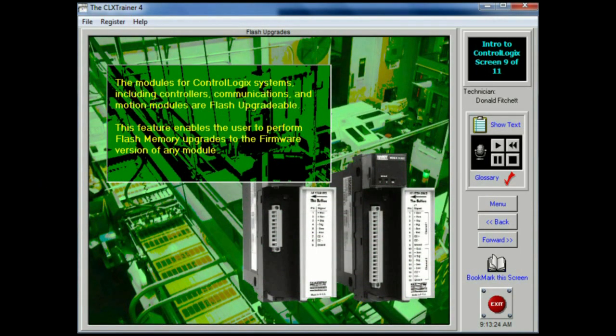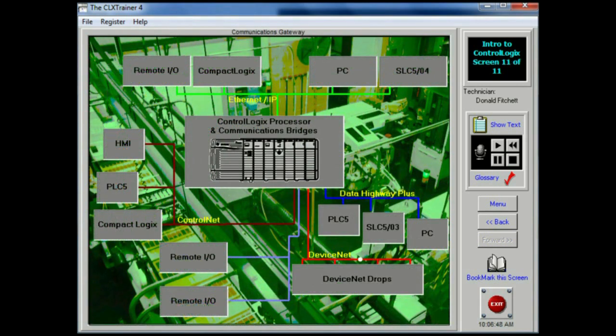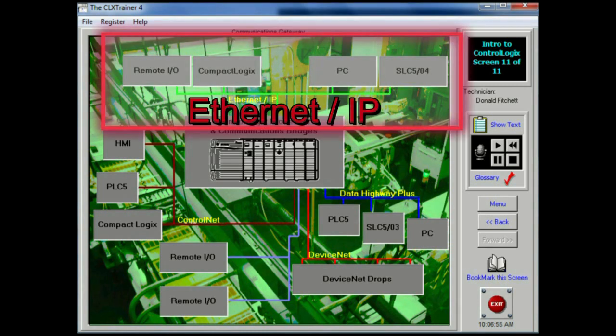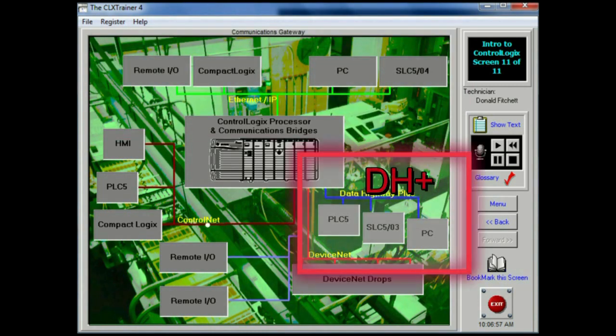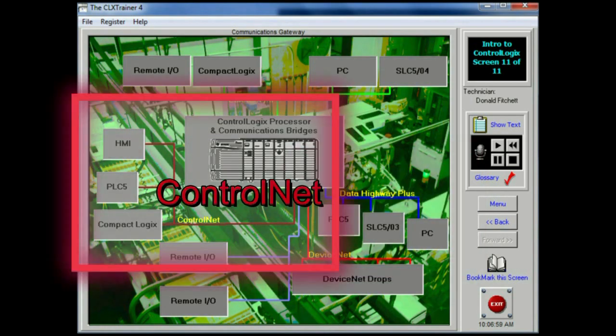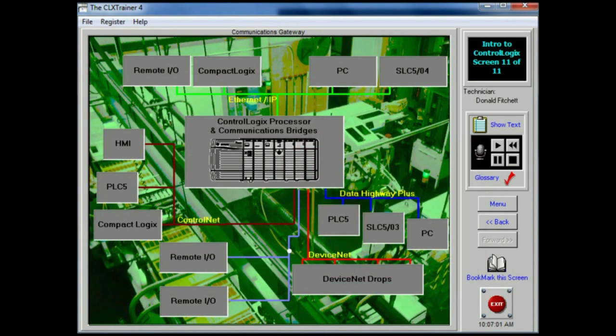The modules for ControlLogix systems — including controllers, communications, and motion modules — are flash upgradeable. This feature enables the user to perform flash memory upgrades to the firmware version of any module. The ControlLogix system can also function as a communications gateway. It can contain the modules needed to communicate with other networks such as remote IO, Ethernet IP, Data Highway Plus, and ControlNet. This allows communications with existing networks so that messages may be sent to and from those networks.